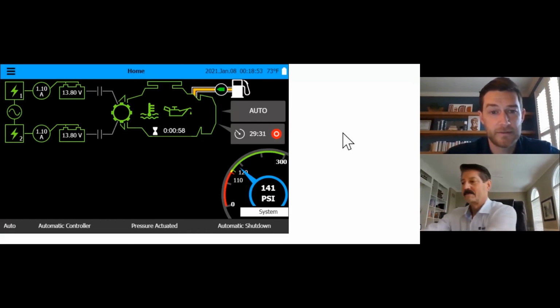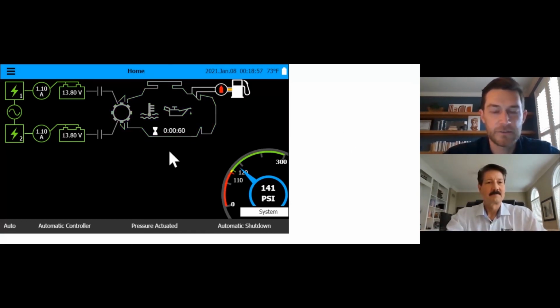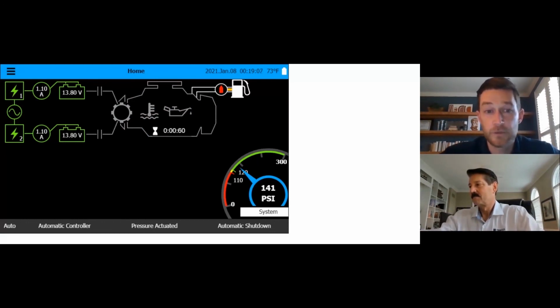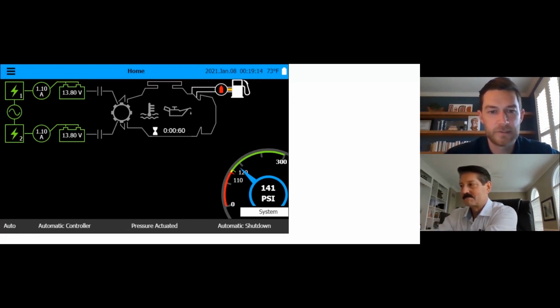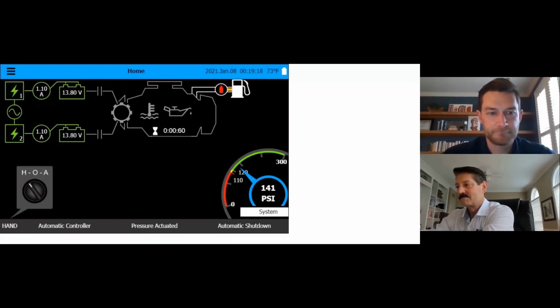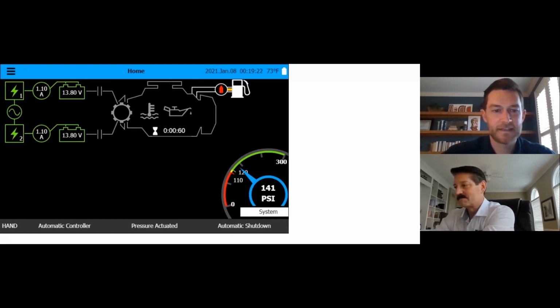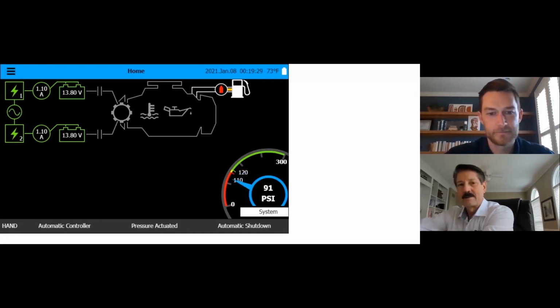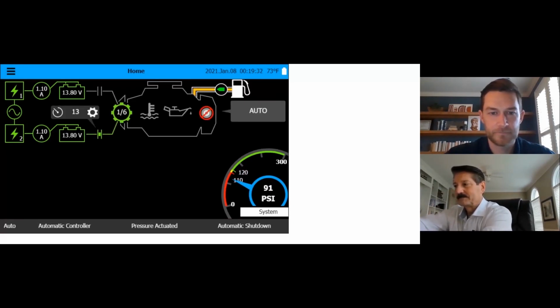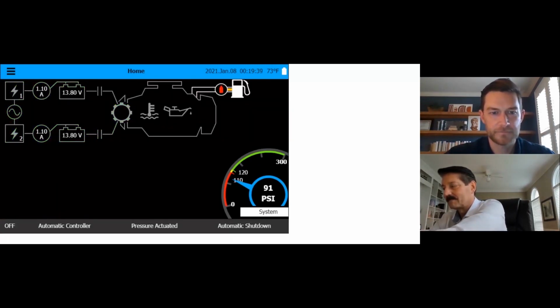Marty, if you want to go ahead, we can stop it now. I think we didn't show a periodic test, like the run test. We didn't do the run test button on the electric. Sure. So I think that's a good thing. With the diesel, we do recommend using the run test button, and we can show you why with a set of alarms. But if you push the run test button and then drop, you kind of have to play with the... yeah, I got to drop the pressure too because it's a demo. Yeah. Hold on. I think it needs to be in auto. Yep. Well, right now it's showing that it was an automatic start. Yep, I got that. Let me jump this up.